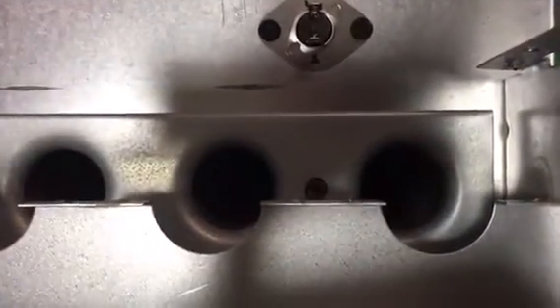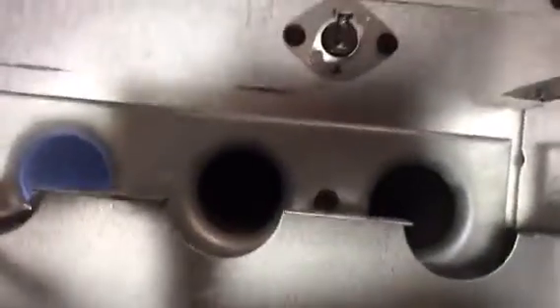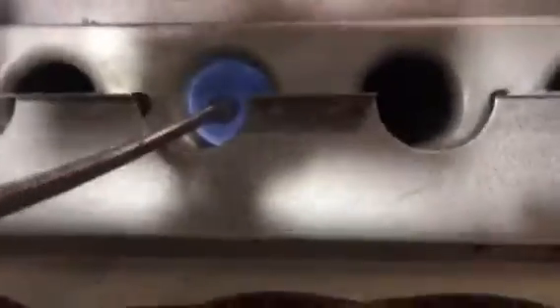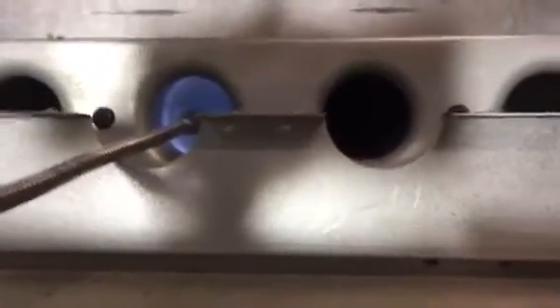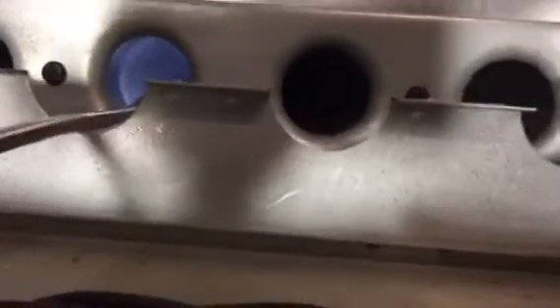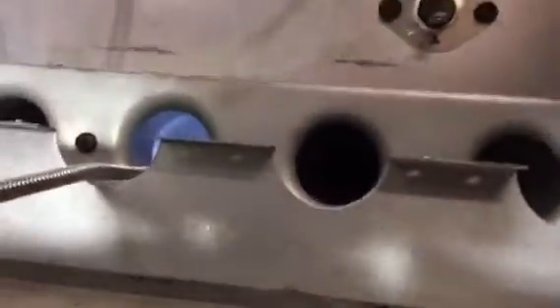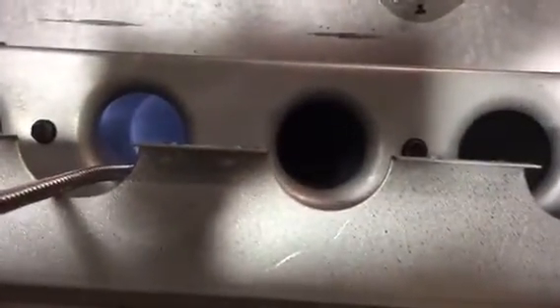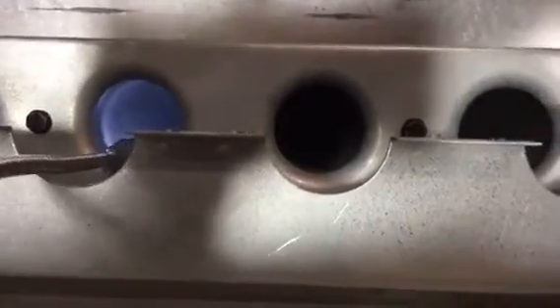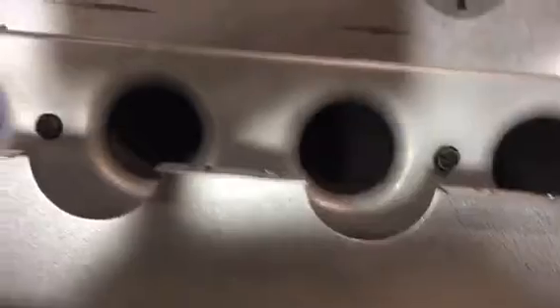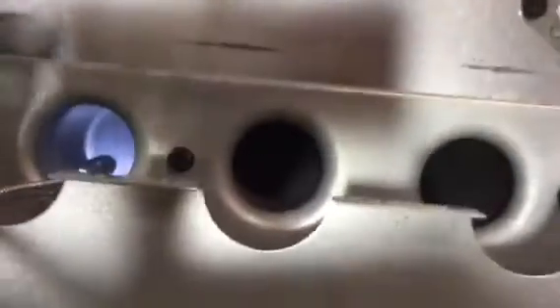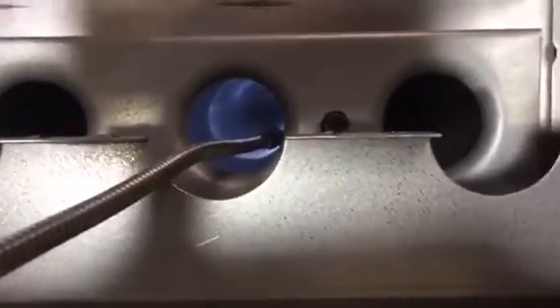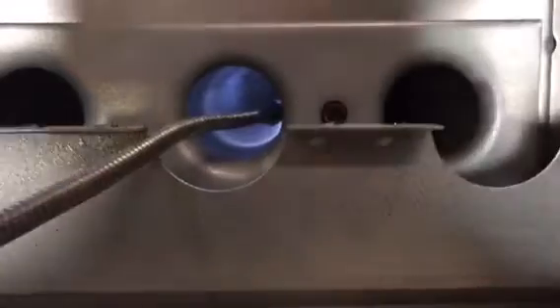Okay, it's a little dark in there, but I've got a little LED light that hopefully will illuminate what we're trying to do here. It's a little difficult to see from this angle, but you can see I'm illuminating the tube. They look pretty good. There's a little debris in there, but there's really not much, and no corrosion, which is the main thing. Now you can only see a portion of it from here. I've got a camera. I can go further if necessary, but given this furnace has only been in service 1 year, I think just giving them a quick look, and here's the number one. Can't see in there too far. Maybe in one of the other ones you get a better view here. It's a little tough. There, you can see a little bit. Okay, so let's brush them out and then vacuum.